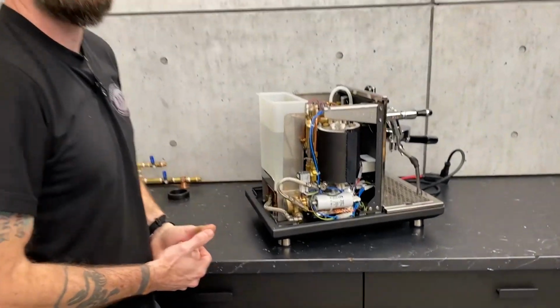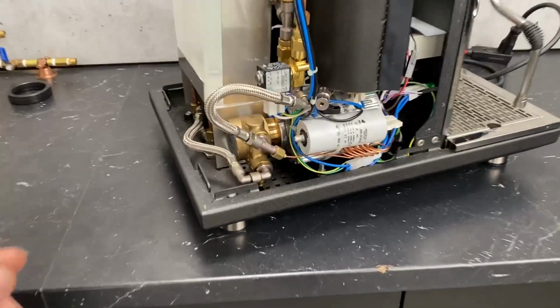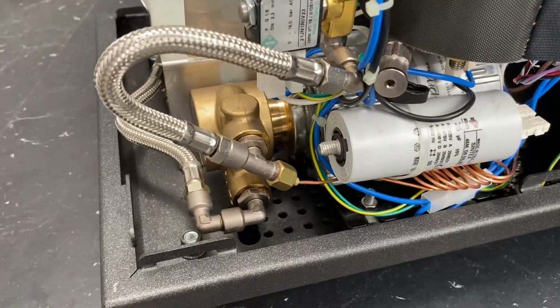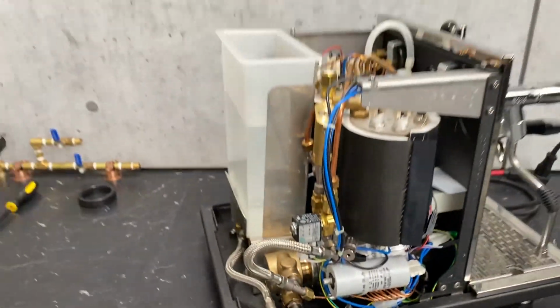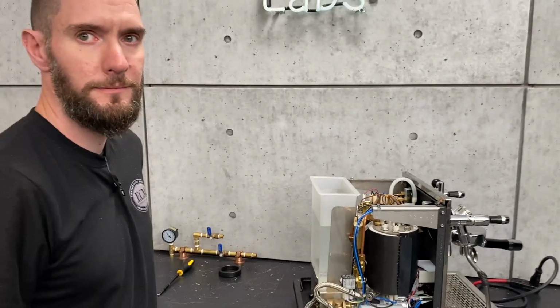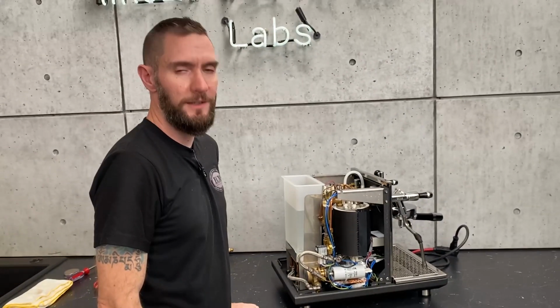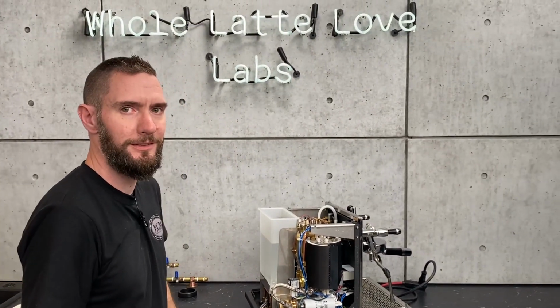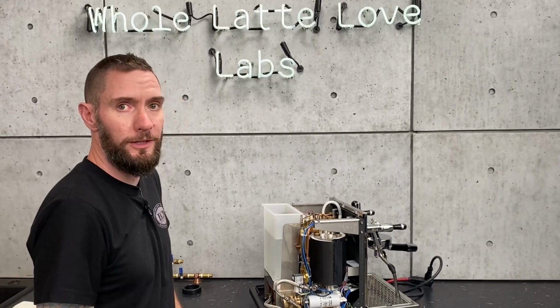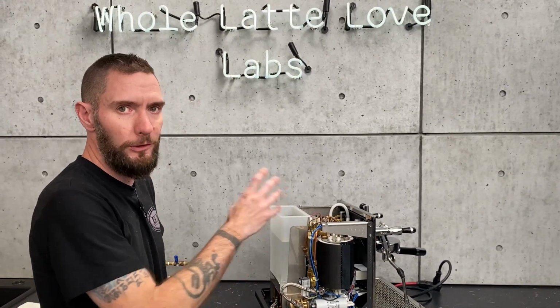Now, correct me if I'm wrong, but this is cooler water being measured back here. It gets to the boiler, it's going to heat up and expand, so it's going to create some pressure, yes? Yes. Ah, so that's the reason you can see a variance between those two gauges.